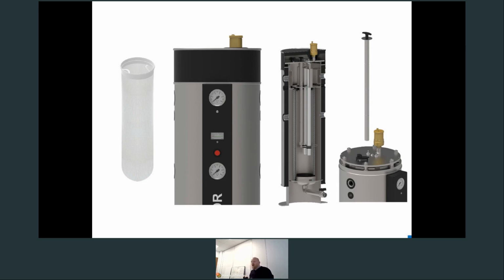Filtration is also a requirement for VDI 2035, and so we have a number of bag filters that can be put into the system as well, and that can create finer filtration. So that can take you down to 1 micron. And what you'll see there in the second image is, on the front, you've got the pressure gauges, and these pressure gauges will indicate the differential in pressure and will indicate when those finer filtration bags need cleaning or replacing.